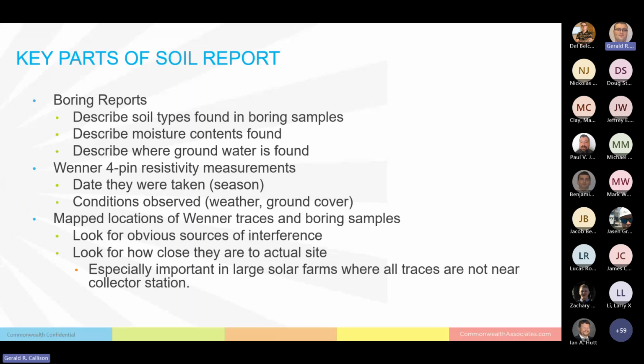Another important thing to look for is the mapped locations of Wenner traces and boring samples. Look for obvious sources of interference in the traces. When I saw a picture of Wenner traces taken right next to the fence of an existing substation, that immediately set off my alarm bells, and sure enough, the numbers did not look good.